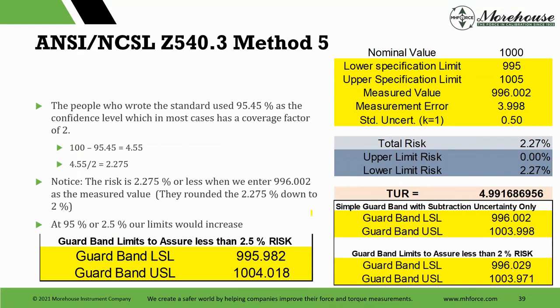So if I use what ANSI Z540.3 says, a 2% PFA, it basically says that if I subtract the uncertainty, my risk should be less than 2%. And when I do that, guard band, lower specification, and upper, and up here I plugged in the measured value. I'm going to switch to a pen because I already have this highlighted. So what I did is I said, okay, let me just subtract the uncertainty. Let me plug this value into the equation, 996.002. And we look at this, and our total risk is 2.2, and if I would have carried it, it would have been 2.275.